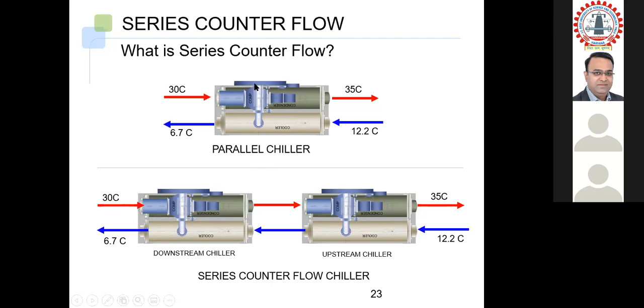Now we call this a parallel chiller. In the bottom one, we have put two chillers in series. In the parallel case, the two chillers are side by side, meaning both receive 12.2 degrees centigrade water and leave at 6.7. The second chiller does the same.